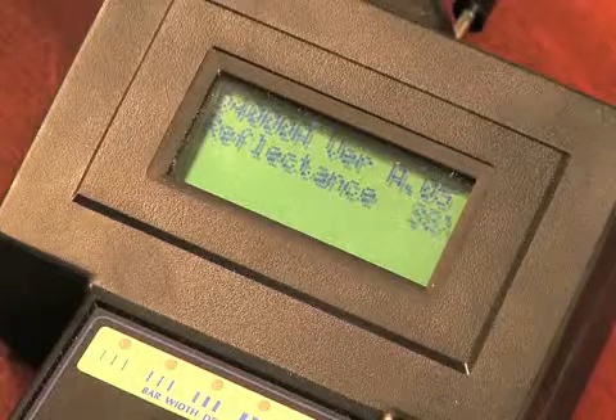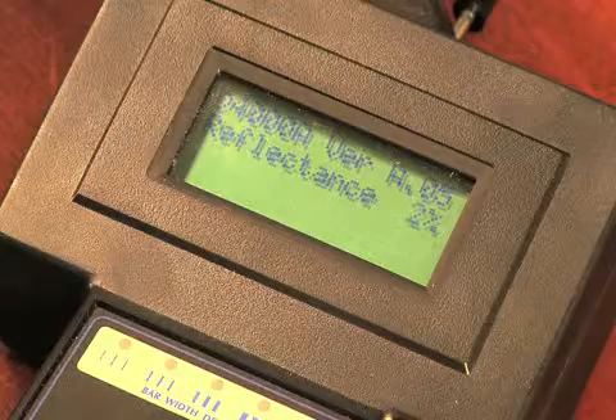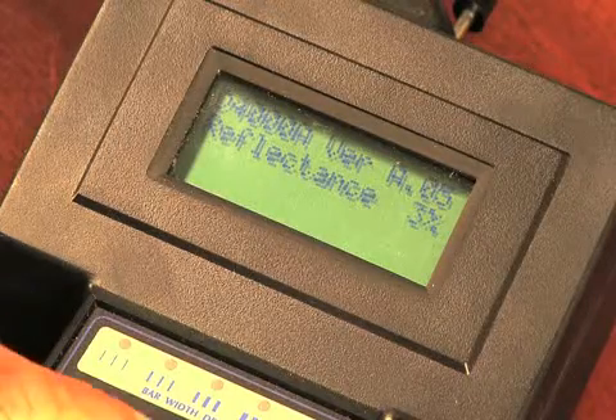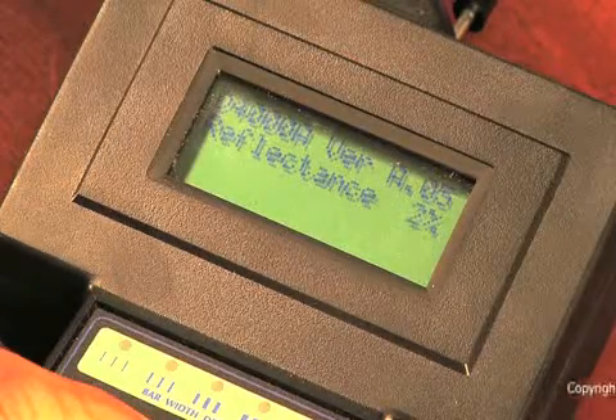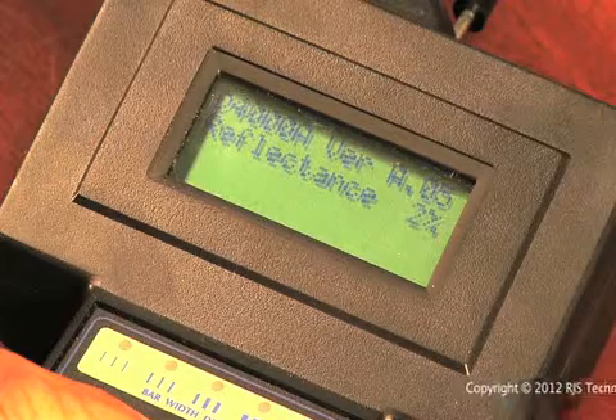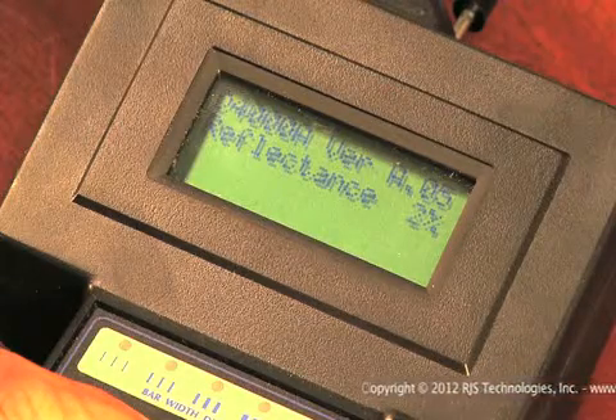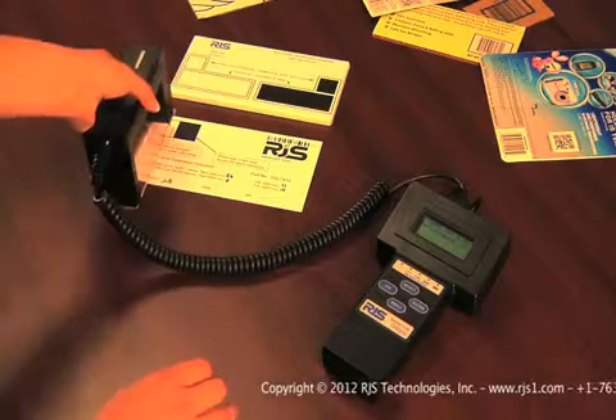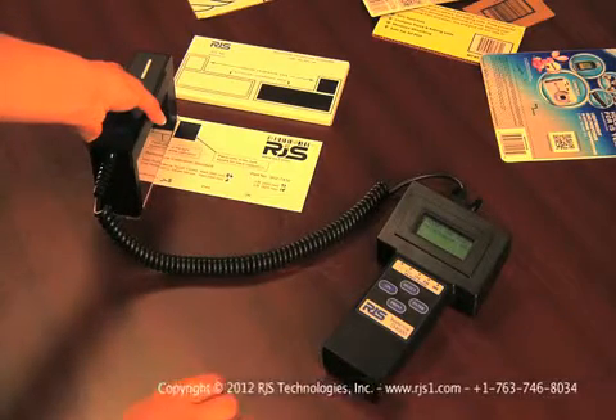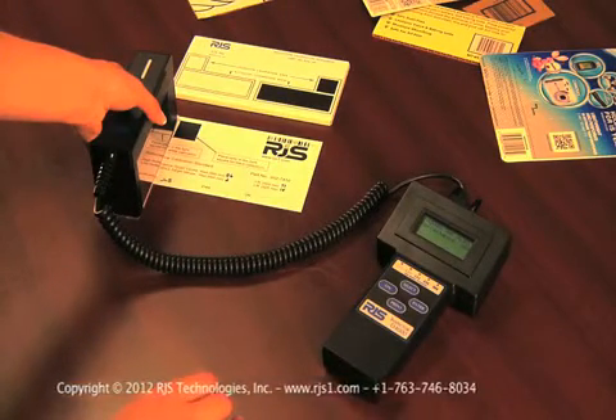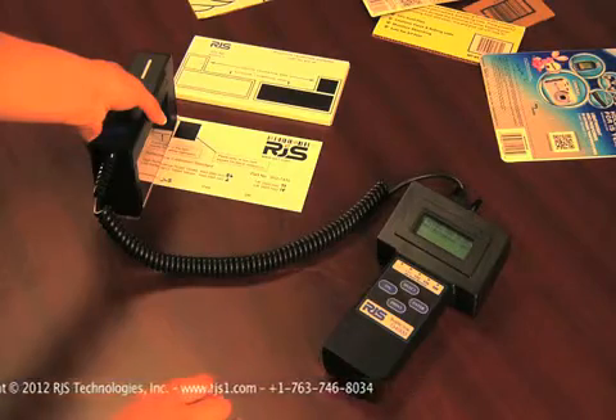This will bring up the reflectometer mode. This can be helpful when designing artwork and selecting background and barcode colors. It's also a way to check the accuracy of your verifier. Place the red light of the Auto Optic over the white square and compare the reflectance percentage to the value written on the calibration plaque.